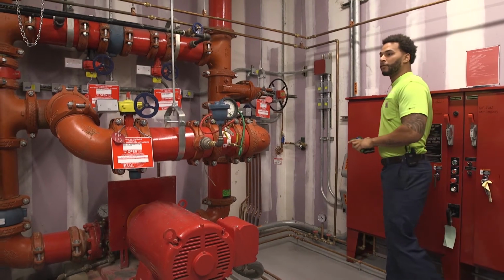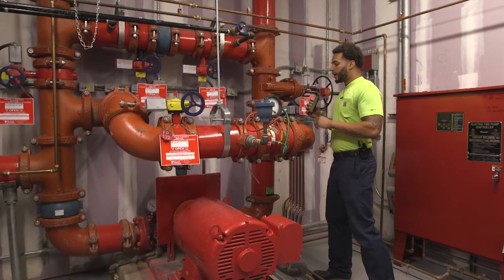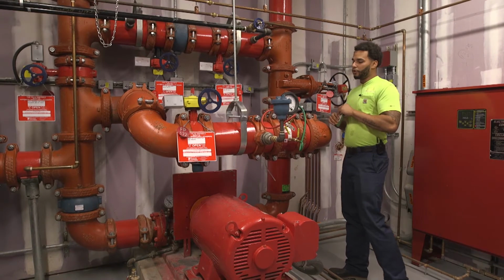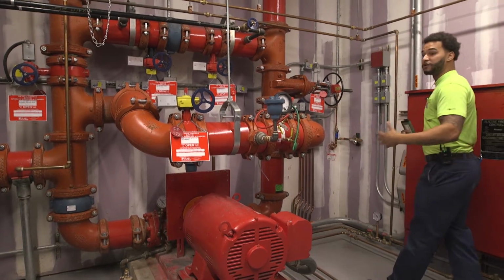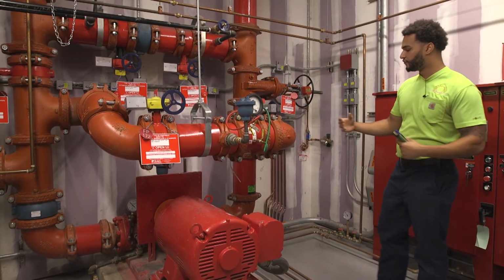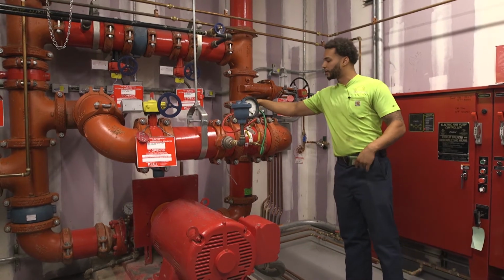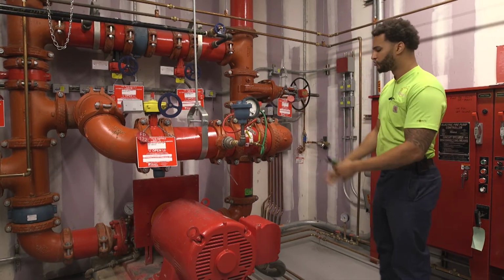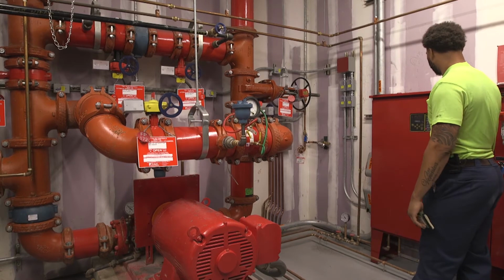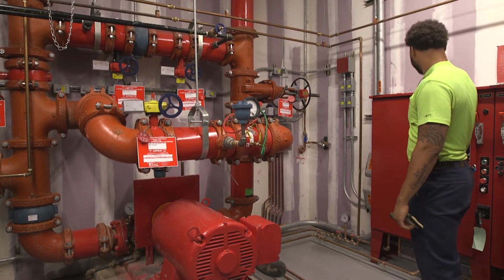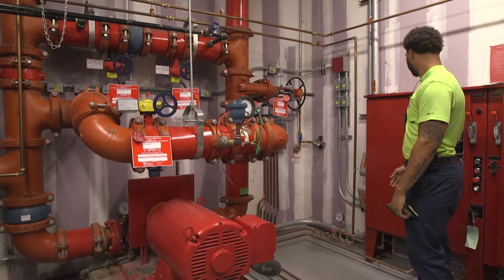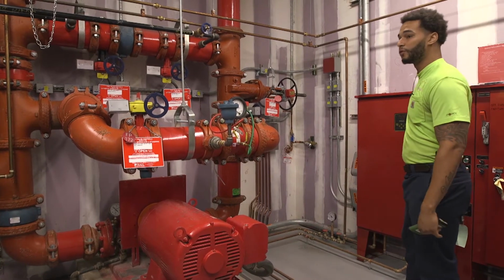And you go offline when you test? Yes, sir. We will always go offline when you conduct any. Weekly inspections just consist of visual inspections. We'll just take a look at the suction discharge gauge, make sure they're reading the same pressure. We'll take a look at our system. So we want our system, currently we got 125. So we wanted to keep them within that range.